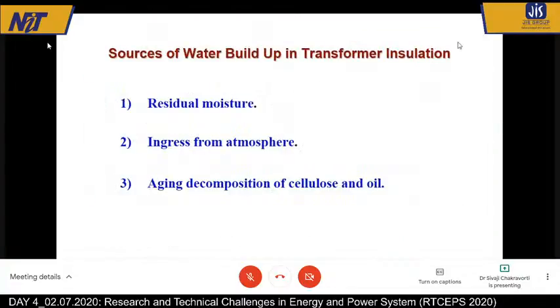Then how does the moisture build up? One is the residual moisture. That means when the transformer was manufactured, we take extreme care, but still, in spite of all the heating process, etc., you cannot make moisture zero from the insulation.